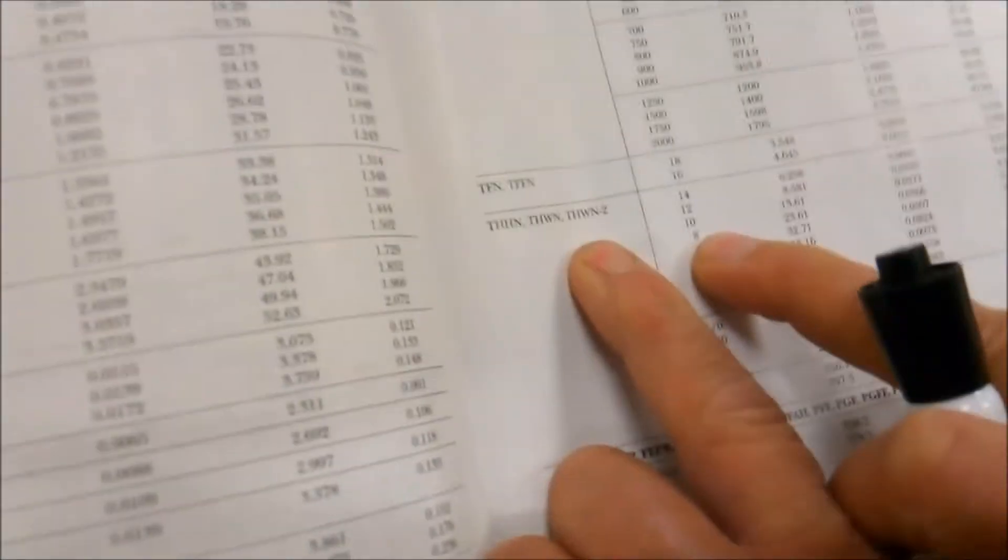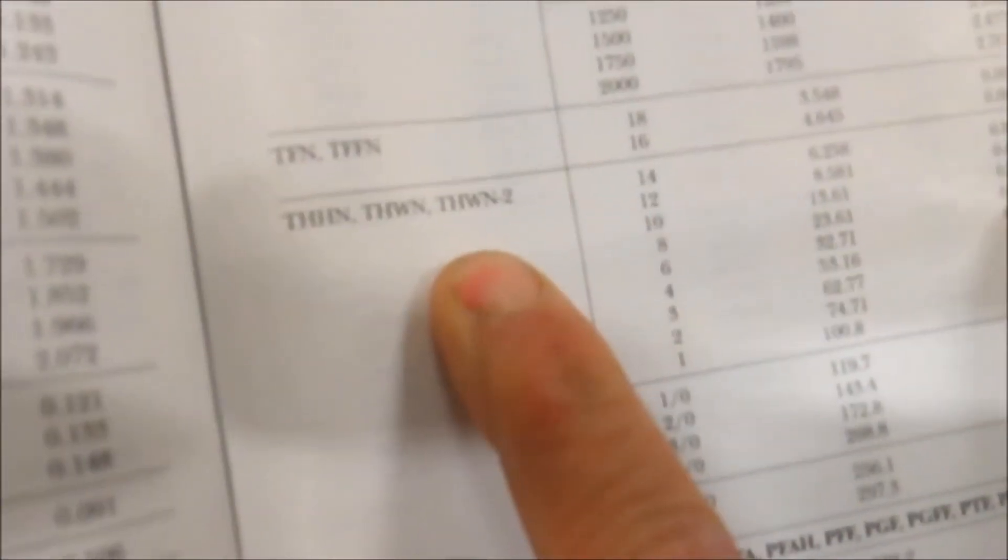And we're going to use metal rigid conduit. So here we go to the chapter 9 tables, and THWN2 is in table 5. Go down here to 8 gauge, and what we want is the area of it, not the diameter, because we want to know the fill.